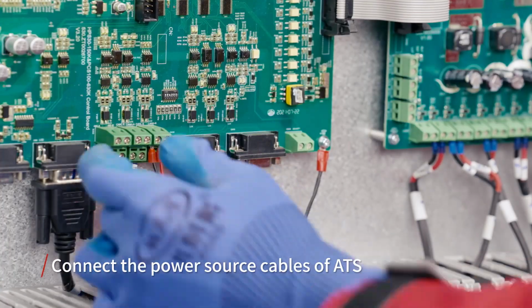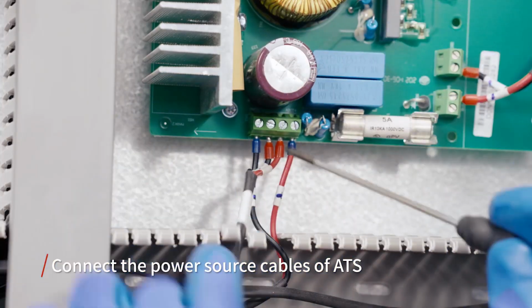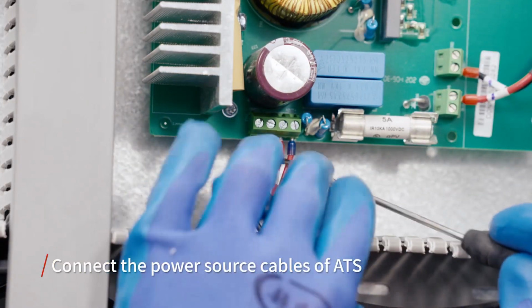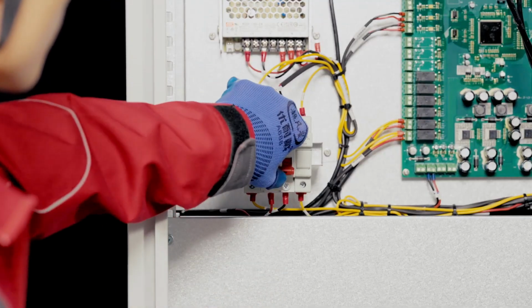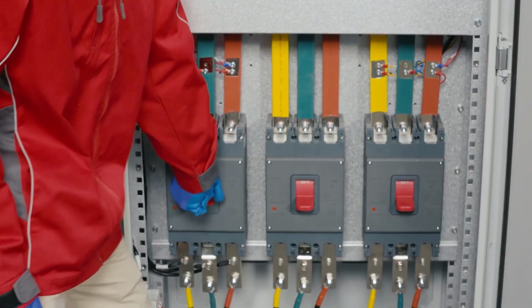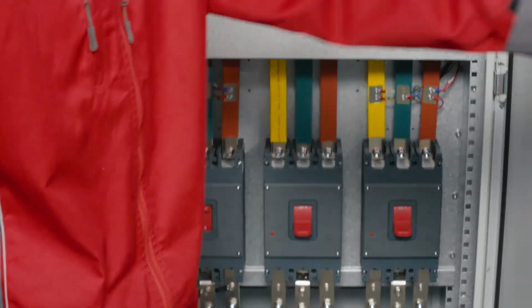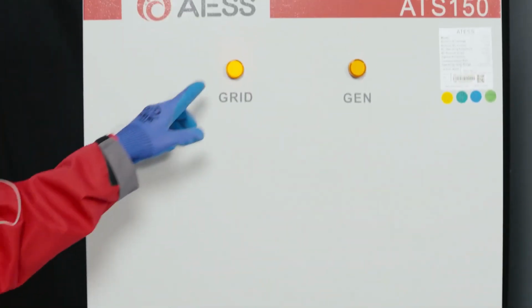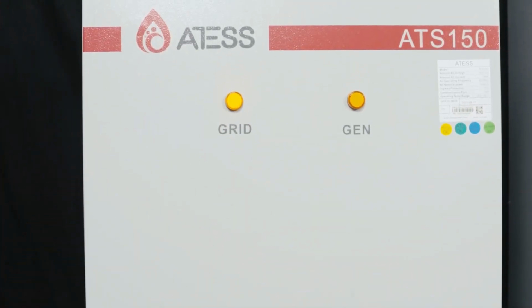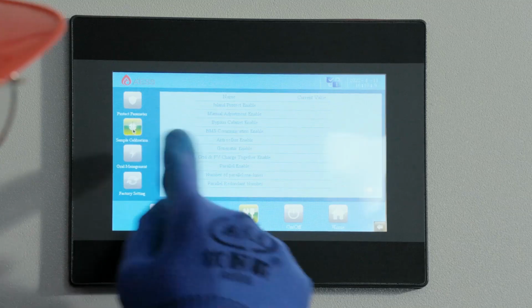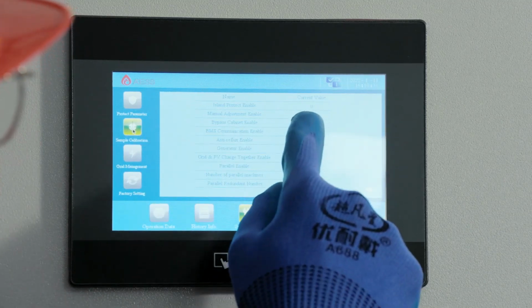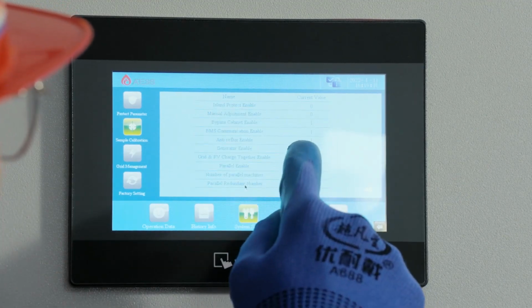Connect the ATS to the power supply. Notice the positive and negative poles. Close the power supply breaker. Close the grid, HPS, and generator breaker of ATS. Meanwhile, ensure that the external grid breaker is disconnected. Set the ATS enable to 1 on the parameter page. The procedure for commissioning is the same as that for commissioning the HPS single unit.